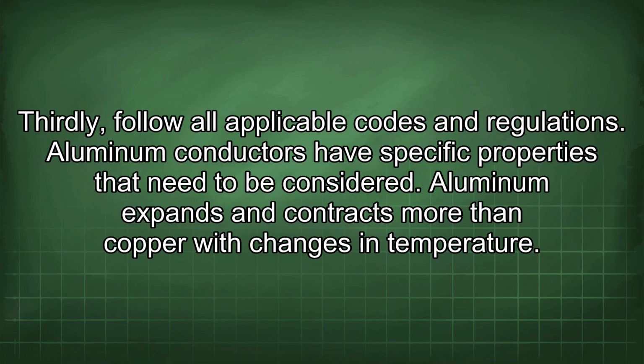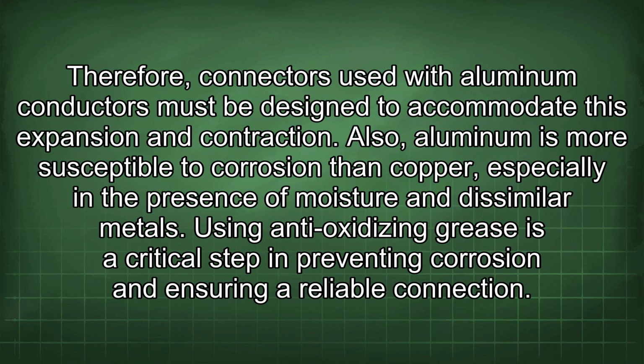Aluminum conductors have specific properties that need to be considered. Aluminum expands and contracts more than copper with changes in temperature. Therefore, connectors used with aluminum conductors must be designed to accommodate this expansion and contraction.